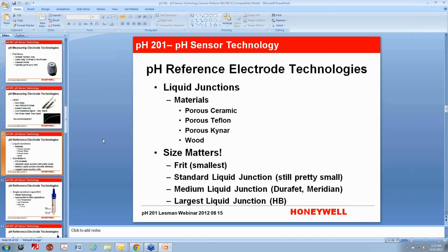and a frit is just terminology for a very, very small hole. And if you look at some laboratory sensors that are completely glass, you'll see the measuring electrode, and then if you look up on the side, you'll see a tiny hole in there. And that hole is your liquid junction, and it allows you electrical contact.